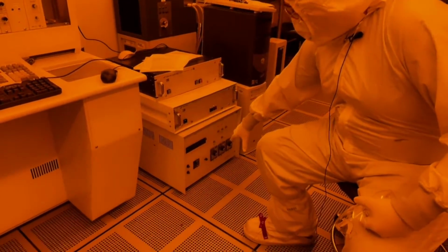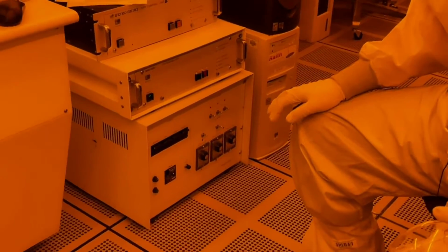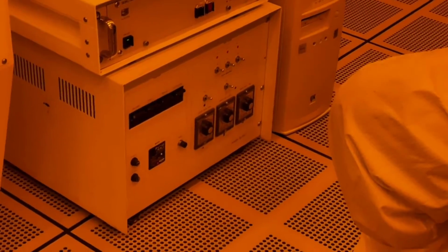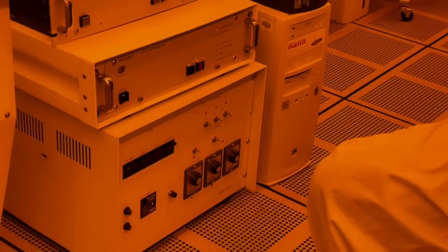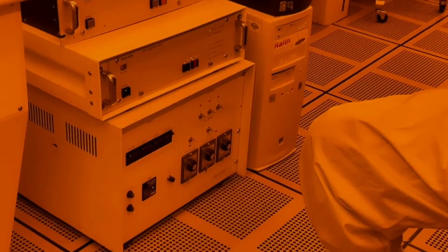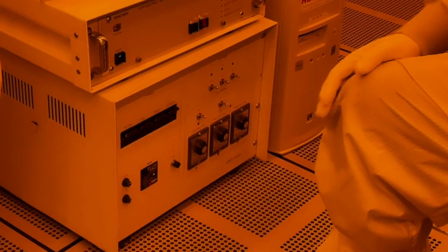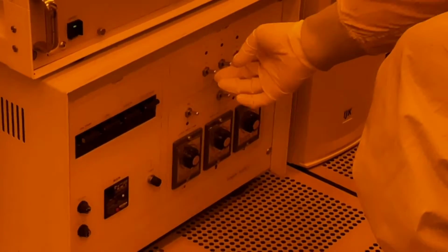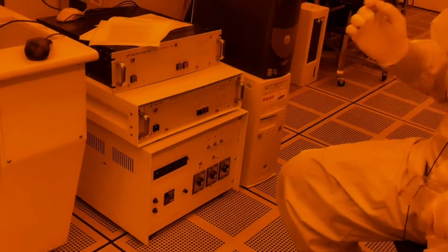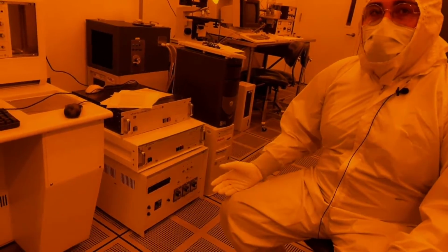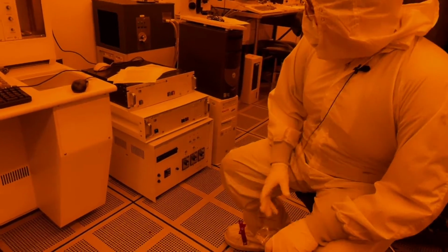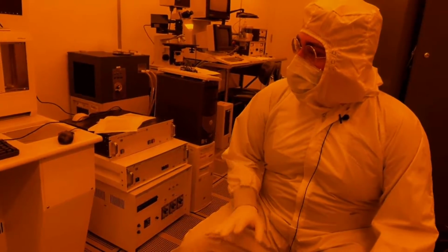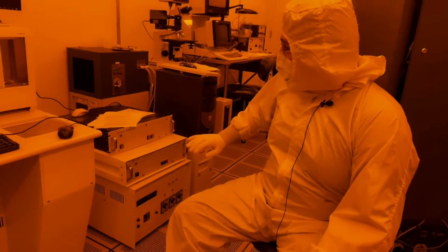On the bottom here, this is the control for our ion pumps. This control is completely dedicated to ensuring that the gun chamber is at vacuum. So what you have here is your 3 ion pump switches. This turns those ion pumps on. This also does the gun chamber baking, which is a common maintenance for these systems. In general, you won't have to worry about this, and we'll go over that in the troubleshooting section. So that's it for most of the panels, at least for now.